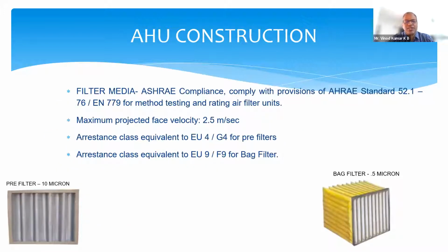Now coming to the last item in the AHU, the filters. Generally, for such applications, the AHU will have a pre-filter and a bag filter, or the fine filter as we call it. The categories are EU4 and EU9, or G4 and G9, according to the manufacturer's standards. But this is what is standard as specified by ASHRAE 52.1 EN779. And here again, the filter selection should be for a velocity of air passing through it of not more than 2.5 meters per second.